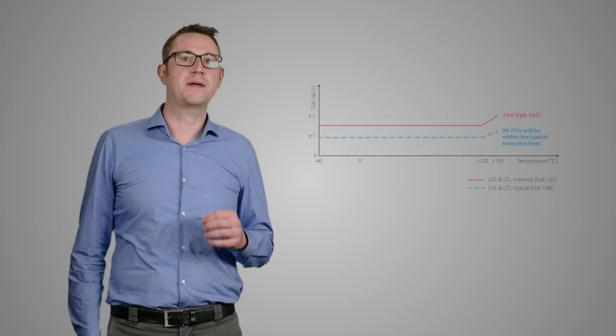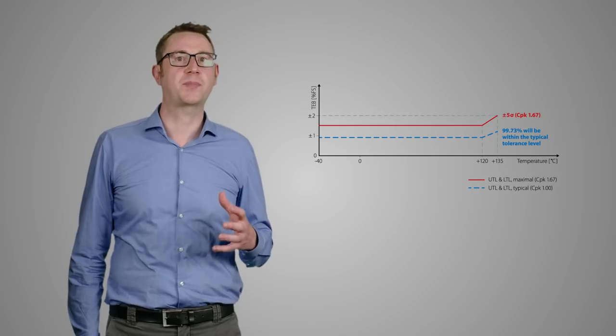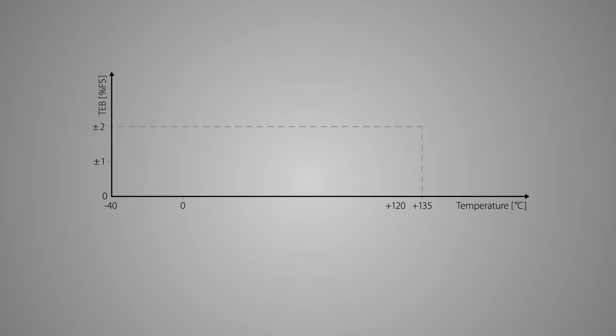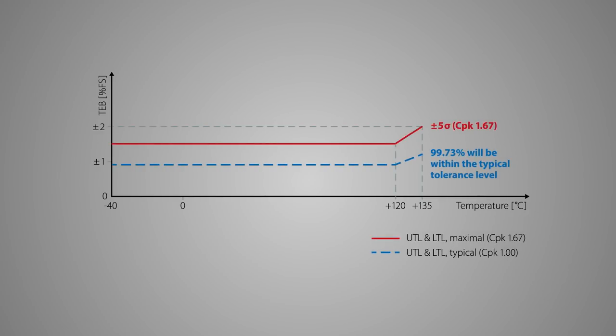In this example, we have a total error band for an exhaust gas back pressure application on an industrial diesel engine. In our datasheet, we indicate both the maximum and the typical value. The red line indicates our total error band here at 1.5% corresponding to 5 sigma limits and CPK of 1.67.